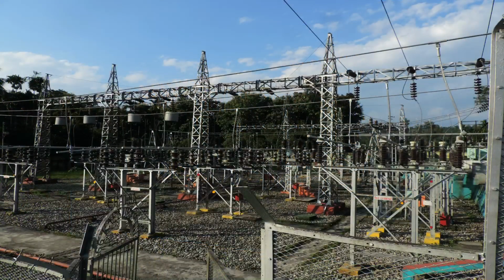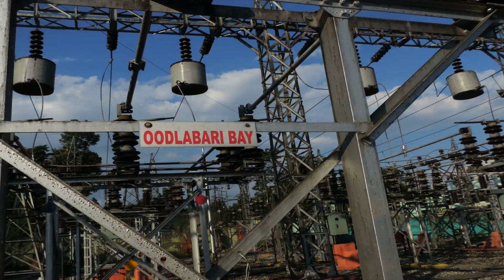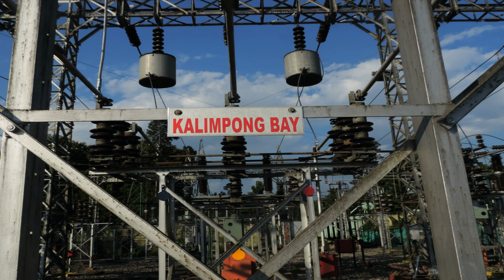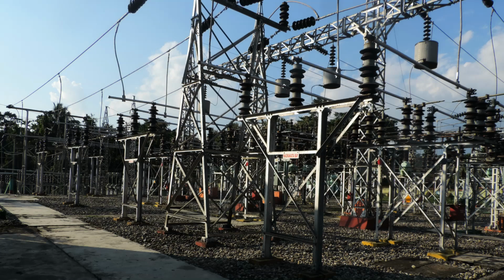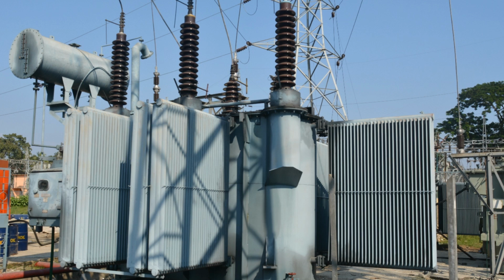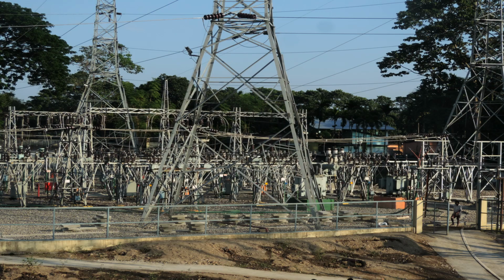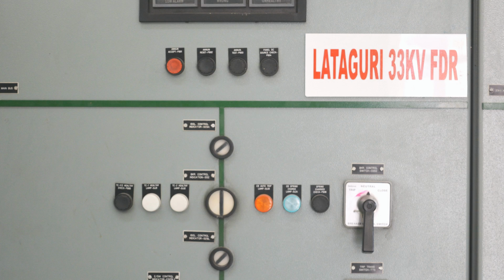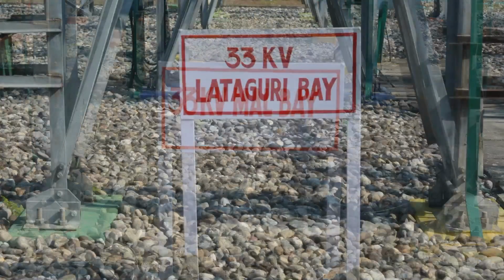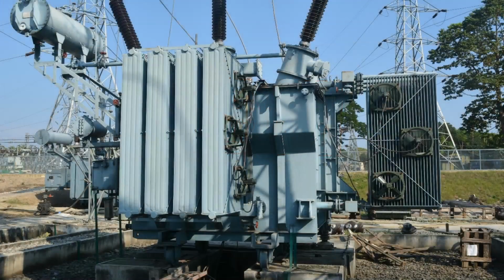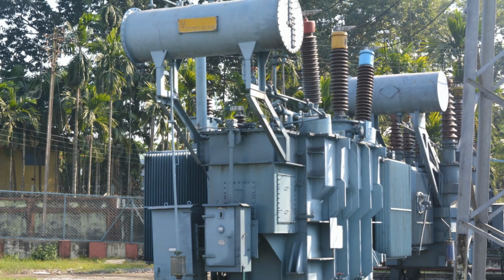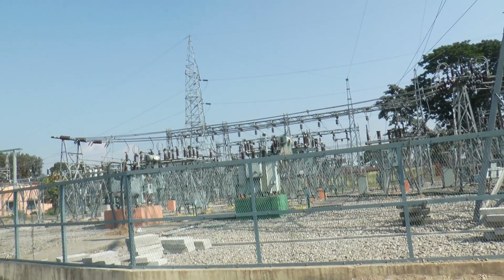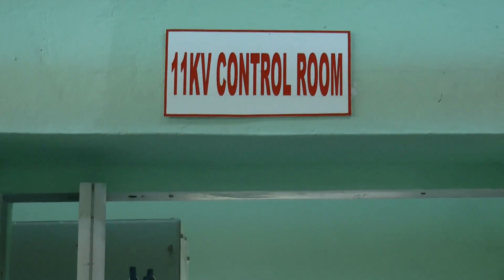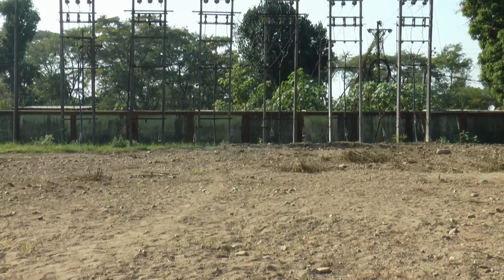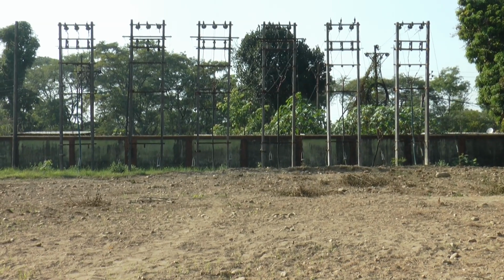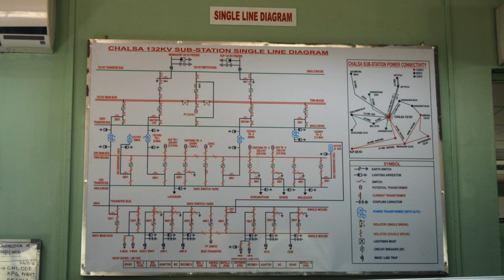Chalsa 132 kV substation caters power via 66 kV line to Otlabari, Nagarkata, Kalimpong and also Banarhat 66 kV substation, fed from two 132 by 66 kV, 20 MVA and 10 MVA transformers respectively. It also caters power via 33 kV line to Malbajar, Lataguri, Korubathan 33 kV substations of WBSETCL, fed through two transformers, 132 by 33 kV, 2 into 20 MVA. It also caters power to local consumers via 11 kV line to 6 11 kV feeders fed through 4 66 by 11 kV transformers, 1 into 4 MVA plus 3 into 5 MVA.